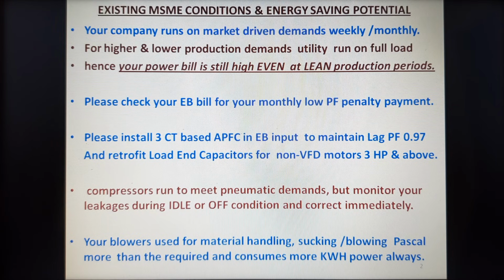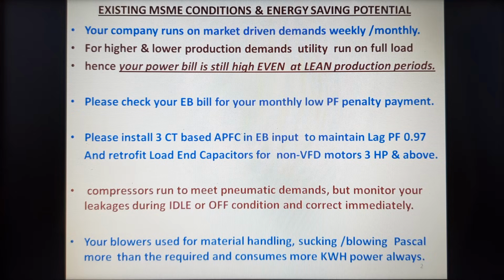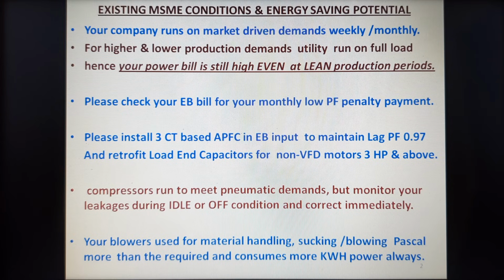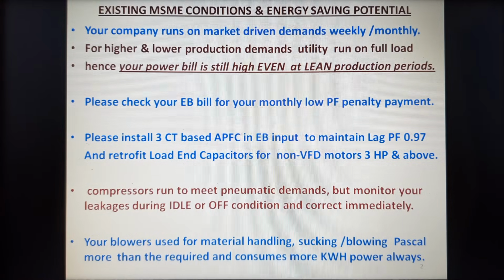For all our blowers, let us try to monitor the pascals delivered at the suction or the delivery of the blower, in such a way that if the suction pascal or delivery pascal is more, definitely this is going to increase our blower power bill, and ultimately the monthly power bill also increases as such.